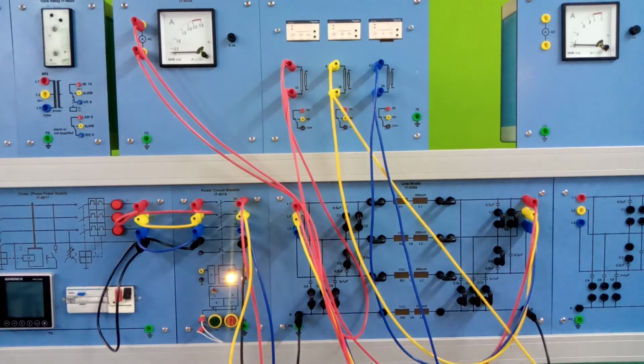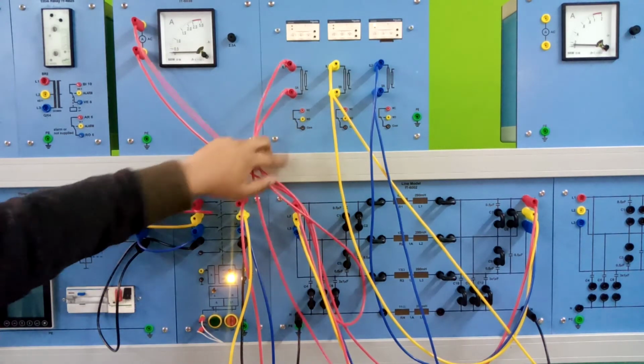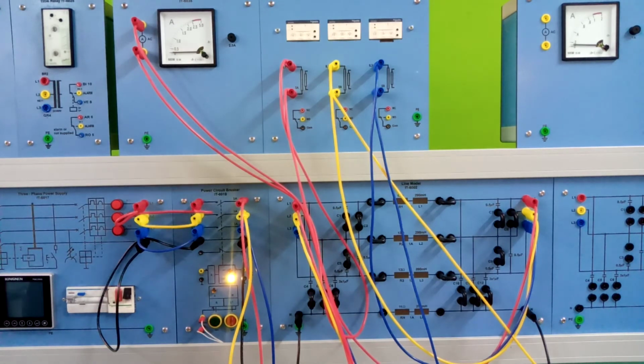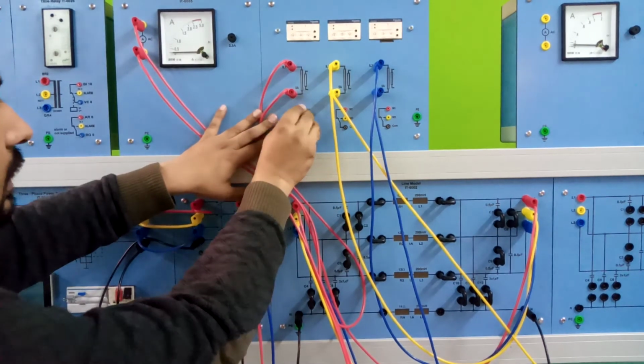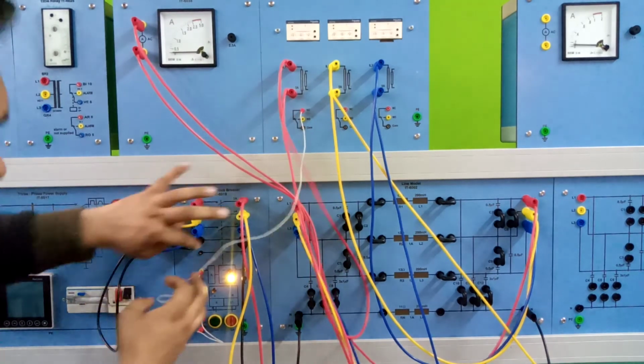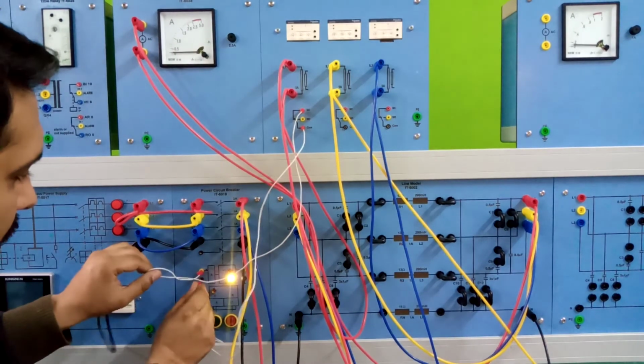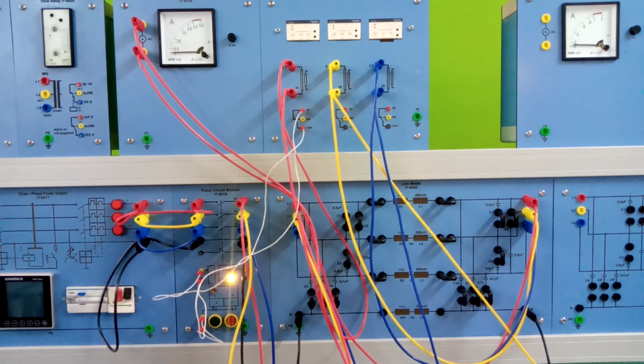Now it's time to connect these breakers. You can see the connection from the PLC terminal will be connected to the red phase normally closed. There you go, this is the normally closed, and then the common of this relay will be connected to the other end of our supply, and then this relay connection will be closed. So this is how we will operate our system, and let's start the experiment.